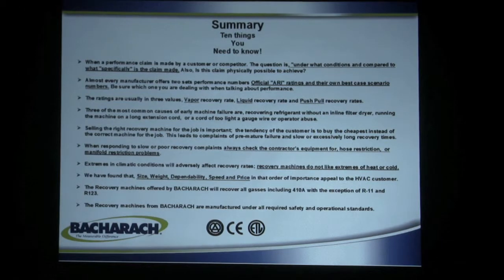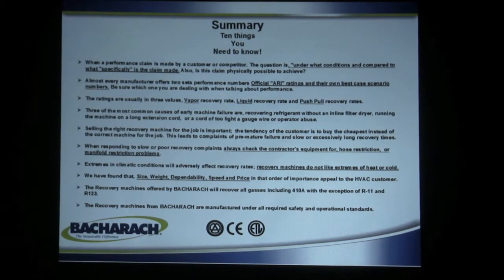Recovery rates are at a specific temperature — recovery machines do not like extremes of heat or cold. Very hot and very cold weather affect performance numbers. A machine tested at 72 degrees ambient is going to act differently at high heat or low temperatures. The size, weight, dependability, speed, and price in that order are what HVAC customers are typically looking for. The recovery machines offered by Bacharach will recover all gases including 410A, with the exception of R11 and R123. Bacharach recovery machines are manufactured under all required safety and operational standards and are certified for performance by the Air-Conditioning and Refrigeration Institute.